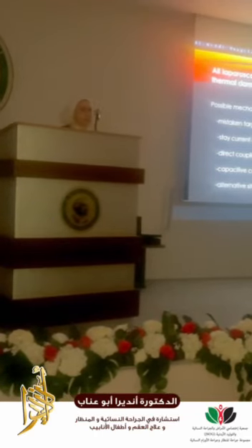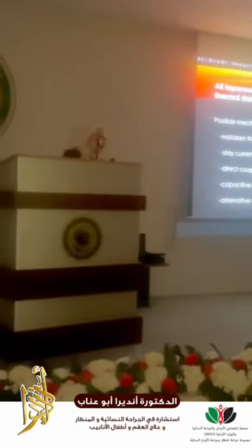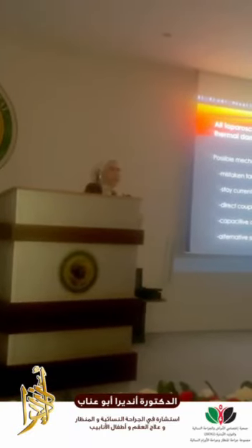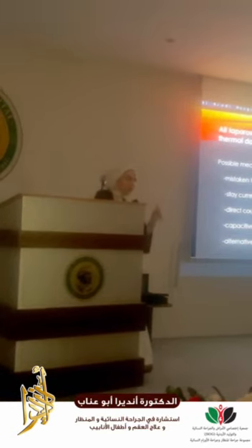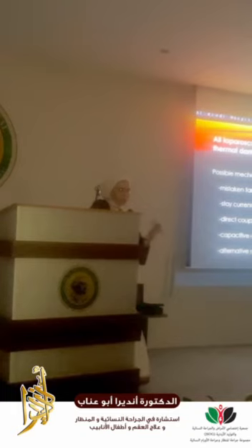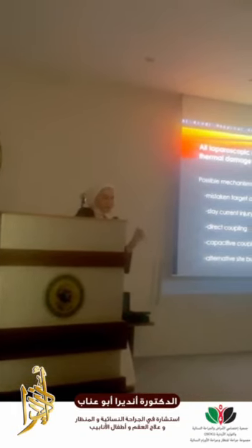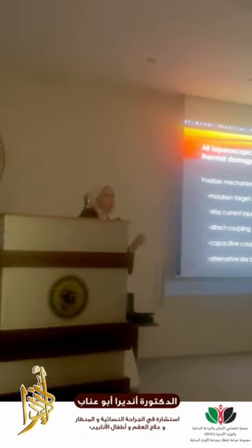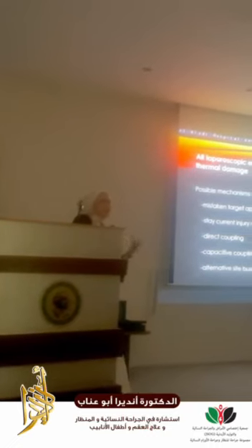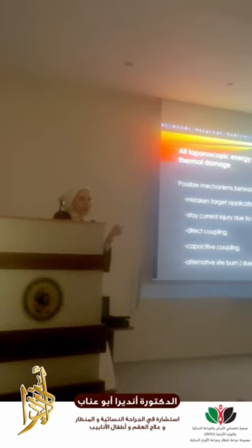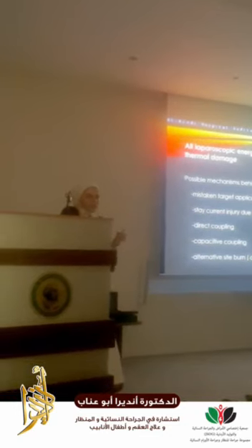So, possible mechanisms of energy injury are mistaken target application and stray current injury due to defective insulation. This is an important point. The instrument where we cut or coagulate should be insulated all through, just the tip should be active. Now, sometimes because of multiple sterilization, this insulating layer may be broken.